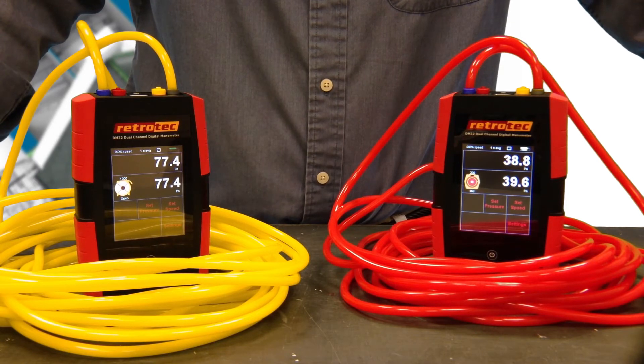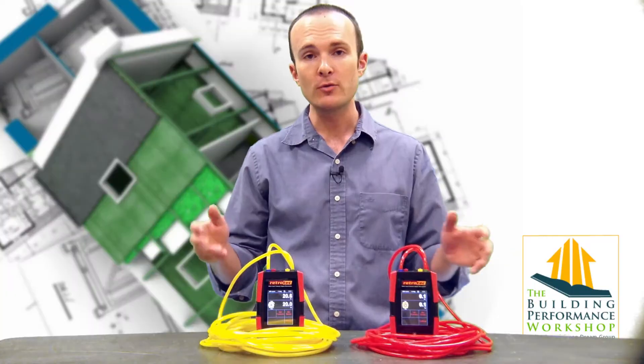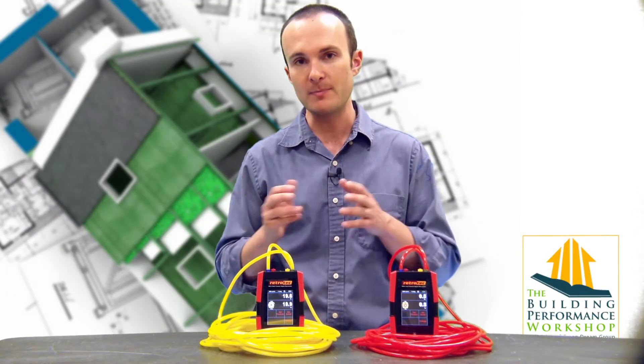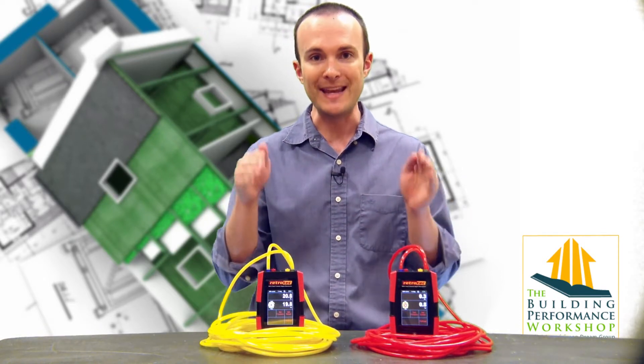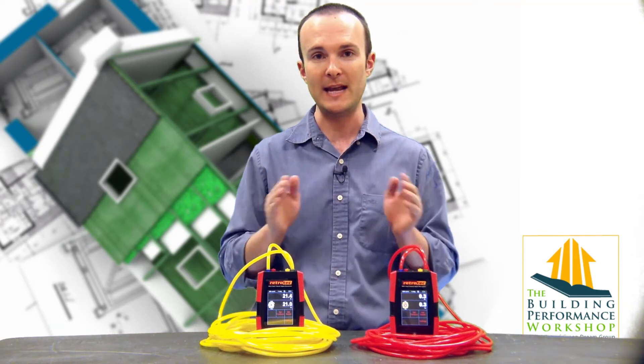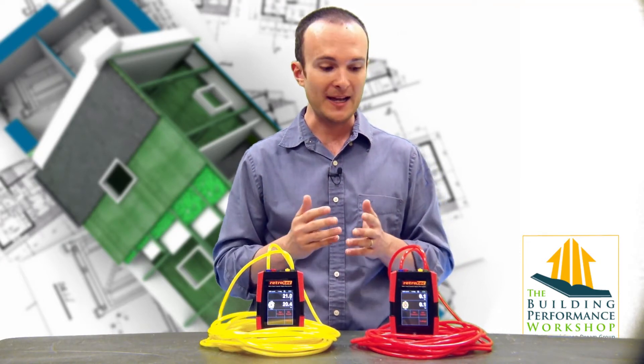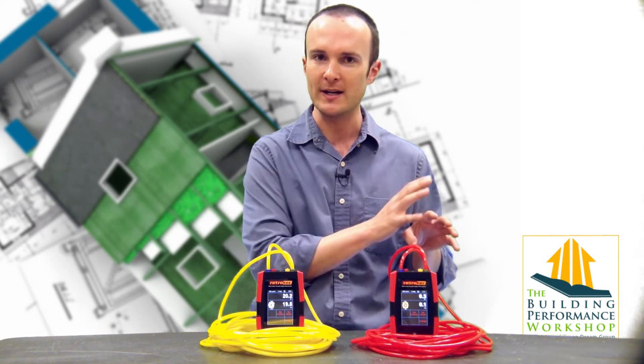The hose that is losing pressure rapidly is the one that obviously has a hole in it. Now you don't need the Retrotec Smart Gauge in order to do this — you can do this with any manometer or even magnehelic gauges if that's what you use. All you have to do is plug it into the input tap or the reference tap of both A channel and B channel, same hose. If you've got extra hoses in the field, great — just go ahead and abandon this hose and move on to the next one.